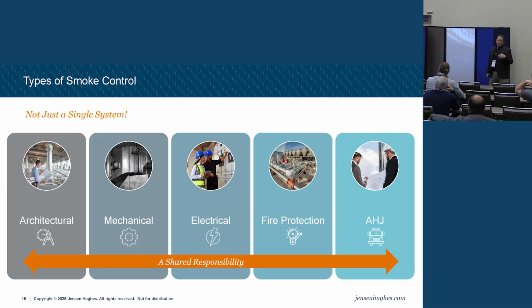So, and I've continually referred to it, but all this slide is saying is when you look at smoke control, you are looking at a whole bunch of pieces to a building solution. And it starts with the architect. The architect may have built in barriers that are required to be smoke-proof enclosures or smoke barriers. Mechanical, obviously I've got air handlers or dedicated equipment whose only job is to do smoke control. So if you've ever been walking around on the roof of your building and been like, what does that fan do? It's never turned on in its entire life. It could be this, right?